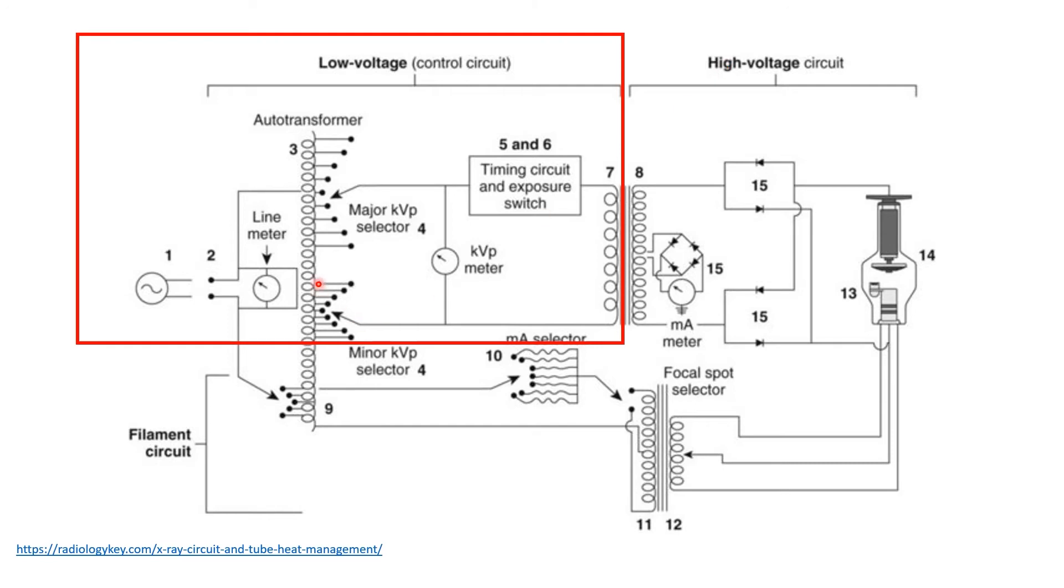The next component is the auto transformer, which varies the voltage to the primary side of the step-up transformer. And this is done by the KVP selector present here in number 4, at the secondary winding side of the auto transformer. Then, it will reach the exposure switch that closes the circuit and lets the current flow through the primary side of the step-up transformer.